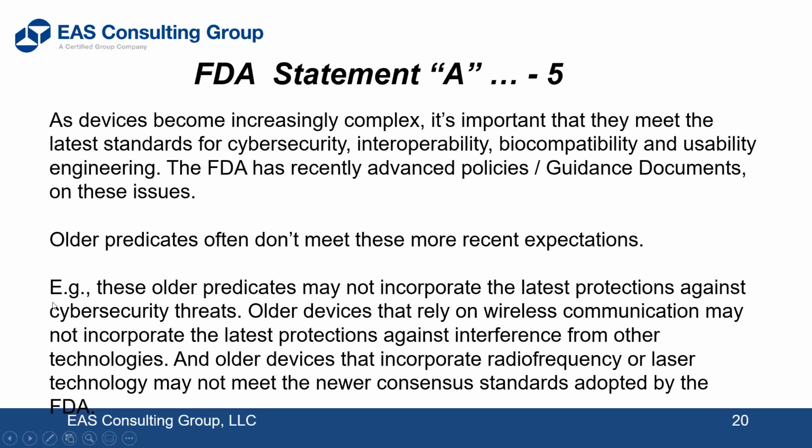And so like it brings out here for example, these older predicates may not incorporate the latest protections against cybersecurity threats. Older devices that rely on wireless communication will not incorporate the latest protections against interference from other technologies, crosstalk and all that. And older devices that incorporate radio frequency or laser technology may not meet the newer consensus standards adopted by the FDA. So that's the danger of using an older device as a predicate.